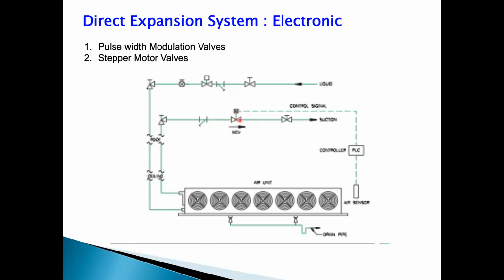In electronic expansion valves, there are two types. We'll just see the pulse width modulated valves and the stepper motor valves. For smaller capacities, normally pulse width modulated valves are used, and for higher capacities, we use stepper motor valves. So this electronic expansion valve has again changed the game in favor of DX systems. Now, as was said, ammonia was always considered for the larger plants and higher capacity plants. Now, with the electronic expansion valve, smaller capacity ammonia plants can also be built and can very easily be executed.